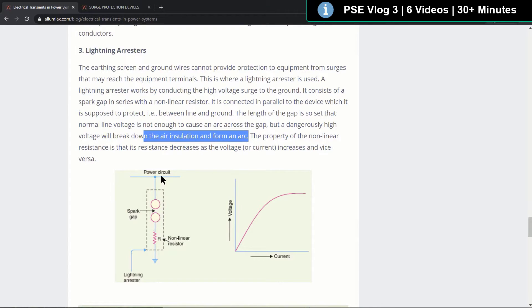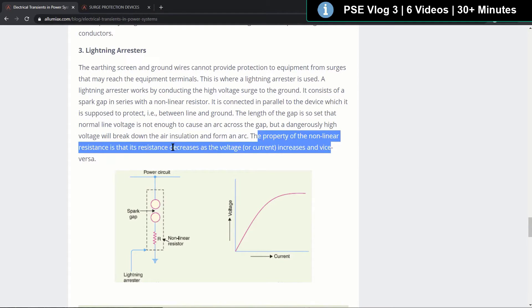So if there's a huge amount of voltage between these two, it'll break down the air insulation here and form an arc across it. And the property of the non-linear resistance is that the resistance decreases as the voltage or current increases and vice versa.